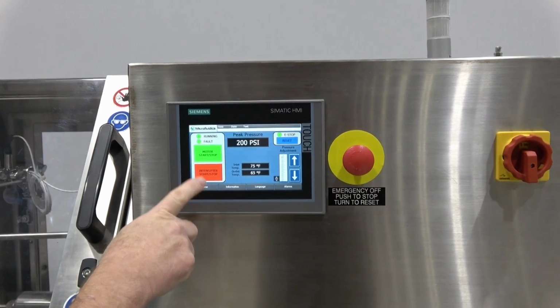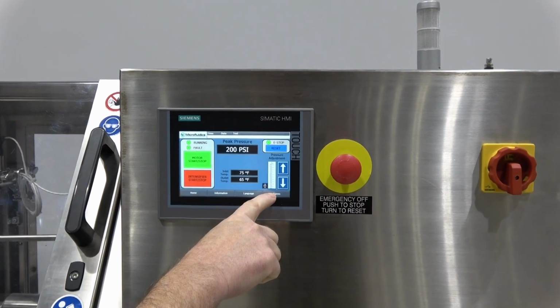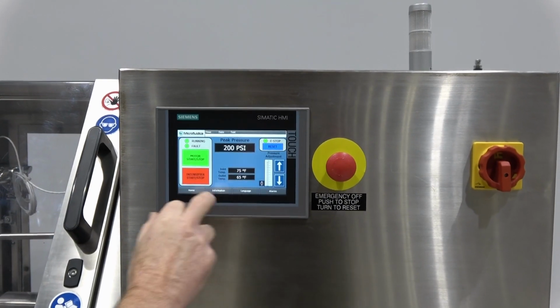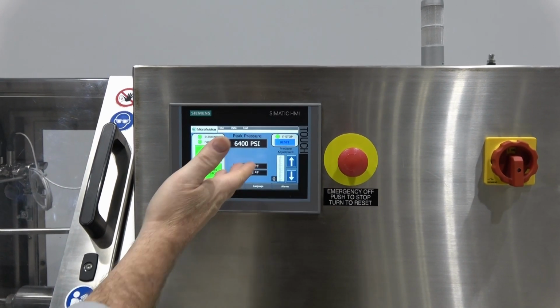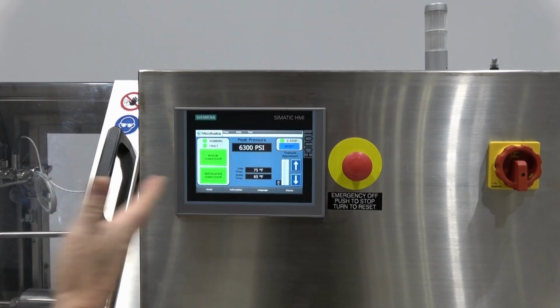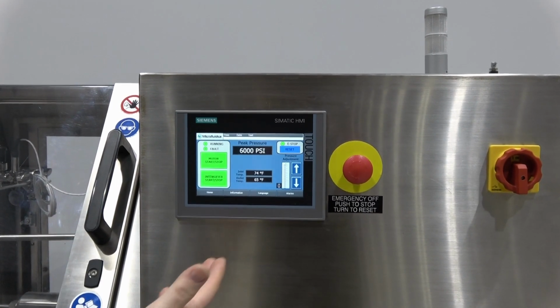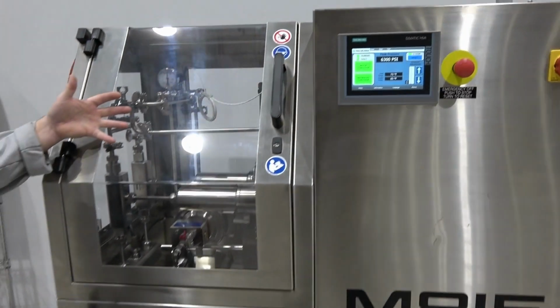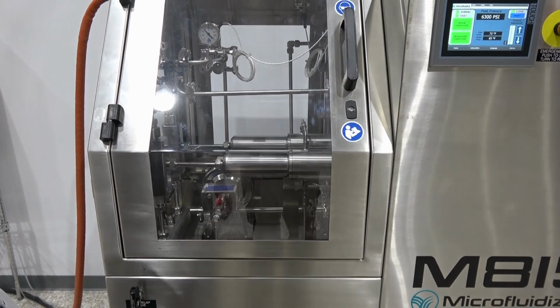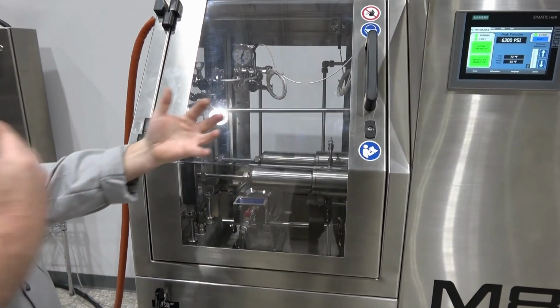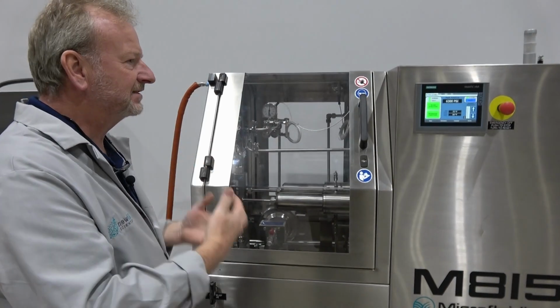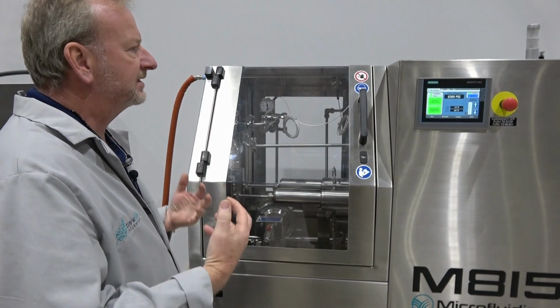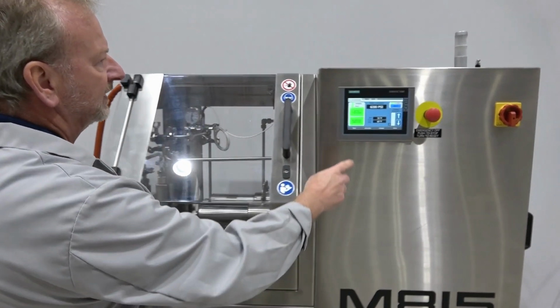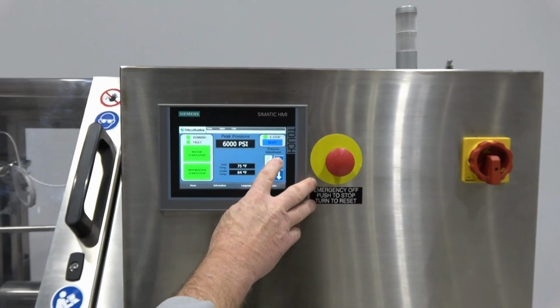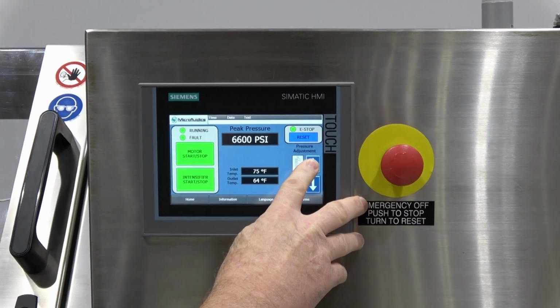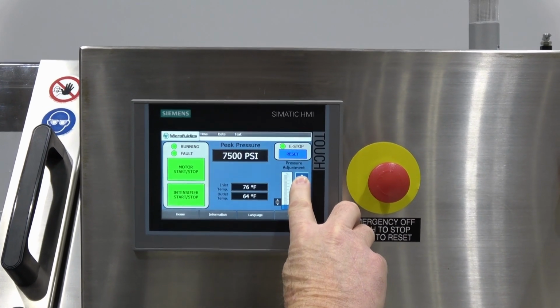That turns the motor, and then we have to hit the intensifier. Right now I have it set clear down at the bottom, so it's going to start off at the lowest pressure. So you can see here we're running at about 6300. You notice how consistent it stays, and that's because of the dual plunger action, where when one plunger's retracting, the other one's still pushing, and you have that consistent pressure, so your product is consistently getting microfluidized when it goes through the interaction chamber. So we're running about 6200 now. We're just going to adjust it on up, and you'll see it slowly climb as our graph slowly climbs with it.